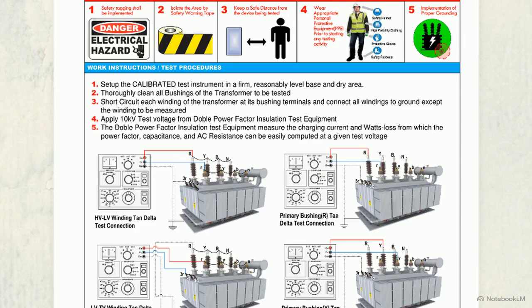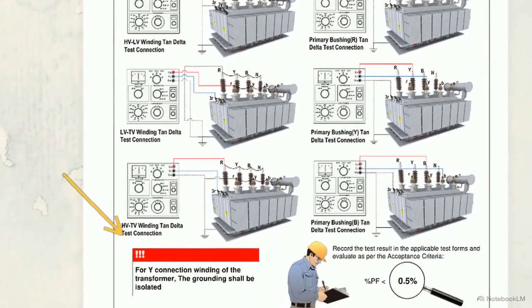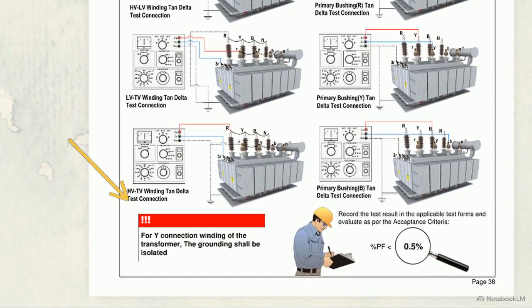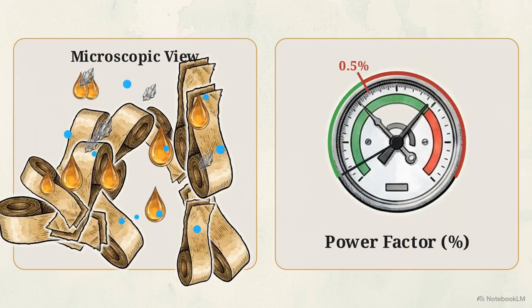Next is the tan delta, or power factor test. This reference diagram illustrates the 10 kV AC injection into the bushing test loops. It also details the requirement to ground or guard any non-tested windings to accurately measure the charging current and dielectric losses. Tan delta testing identifies microscopic moisture and contamination inside the paper and oil. For a healthy oil-filled transformer, the measured power factor must remain strictly below the 0.5% limit.